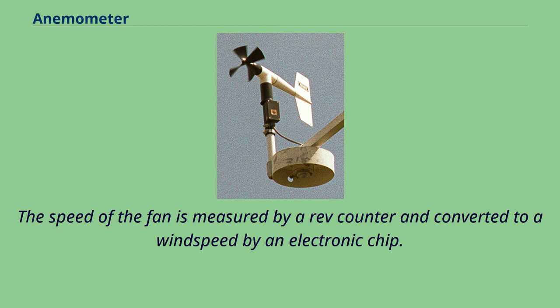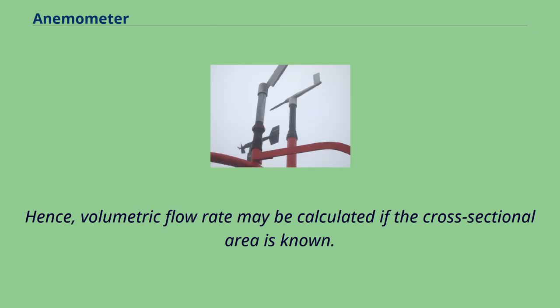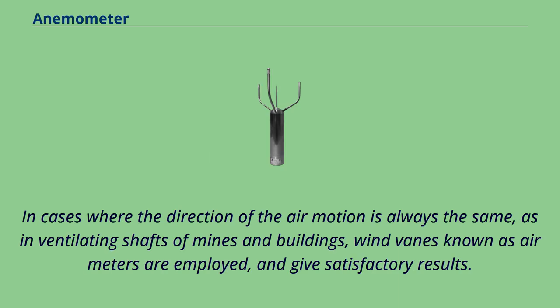The speed of the fan is measured by a rev counter and converted to a wind speed by an electronic chip. Hence, volumetric flow rate may be calculated if the cross-sectional area is known. In cases where the direction of the air motion is always the same, as in ventilating shafts of mines and buildings, wind vanes known as air meters are employed and give satisfactory results.